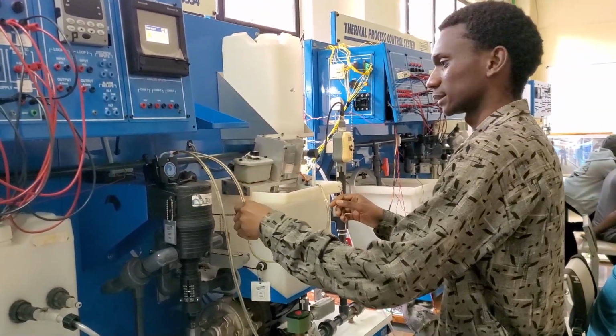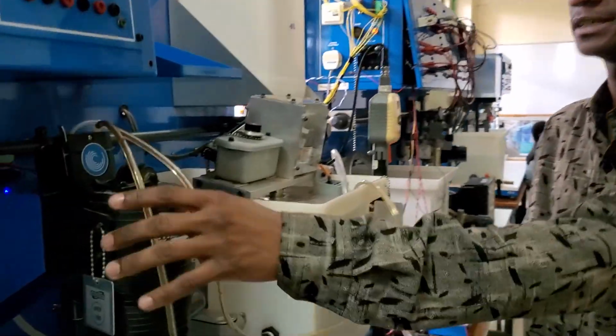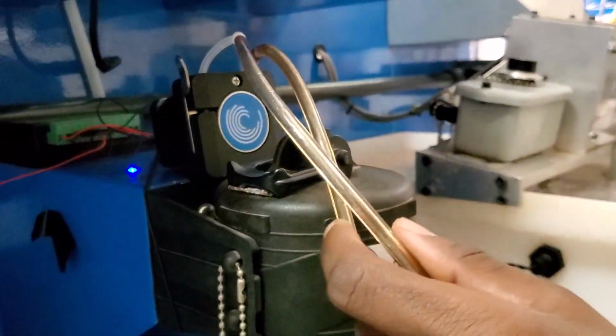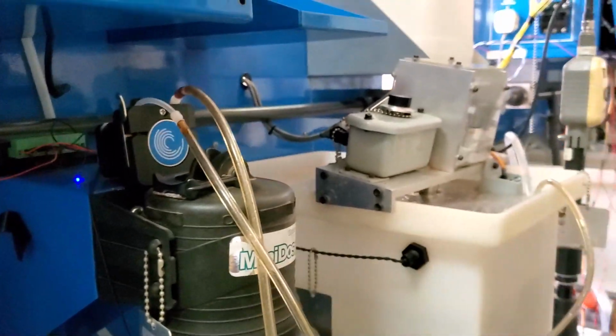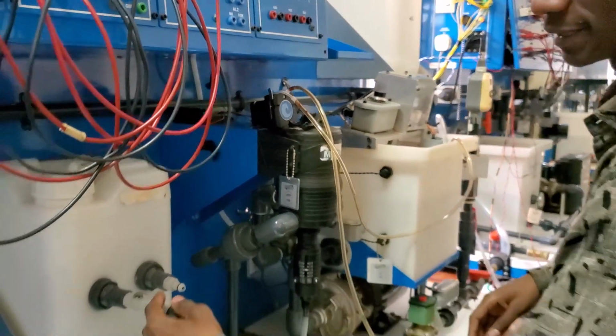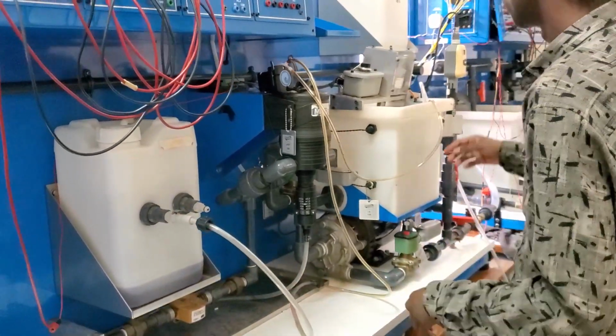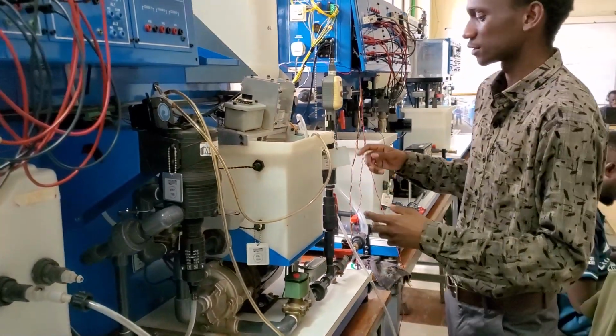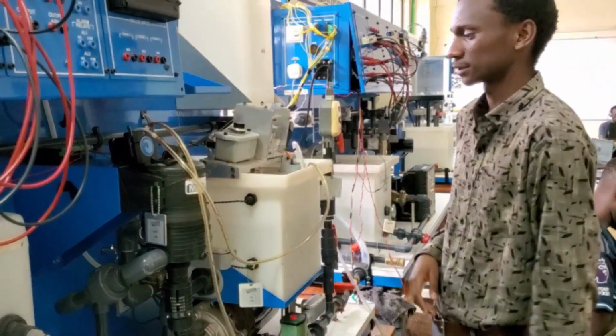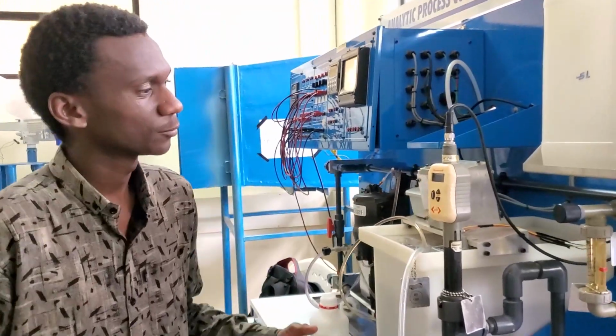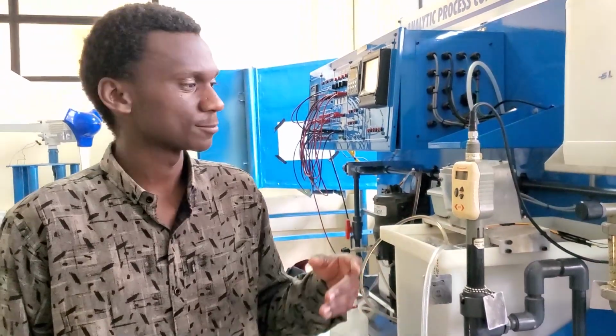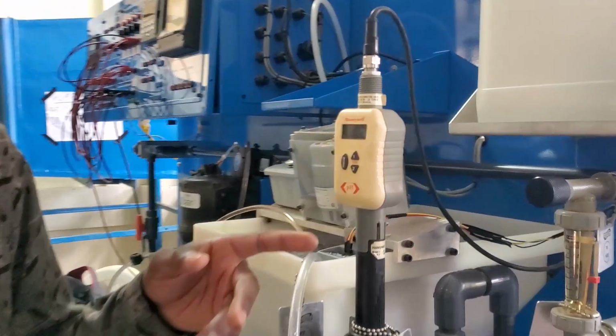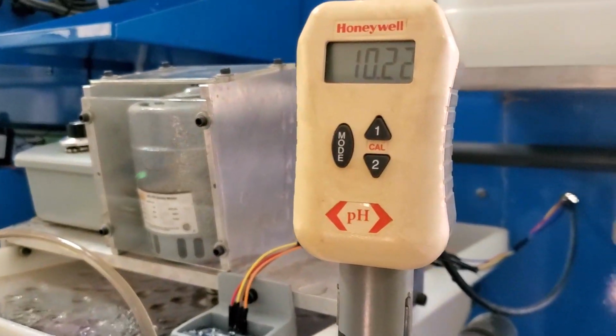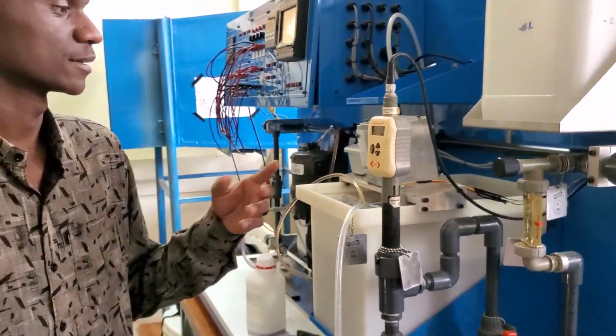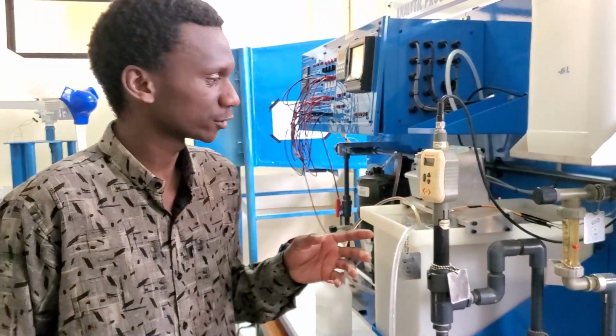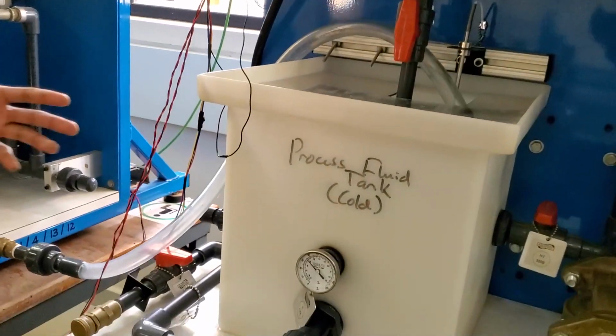So the circulation starts here. The pump starts circulating based on the PID that we've implemented to regulate the pH, whereby we are pumping the concentrated calcium hypochlorite solution into the distilled water to reduce the concentration to the required set point. The system will stop circulating once the required range of the set point has been reached. As you can see, the pH has changed. Hence, the next sequence will be the transferring of the solution to the thermal station.